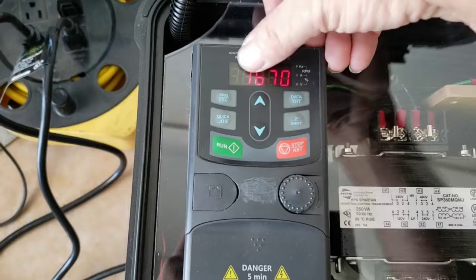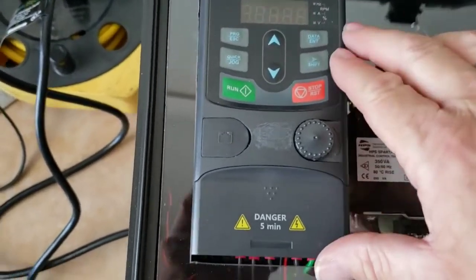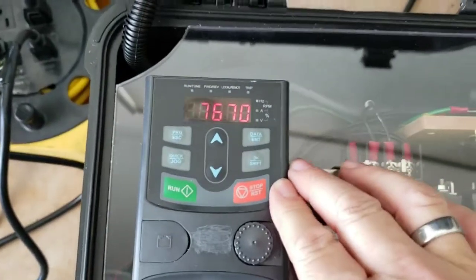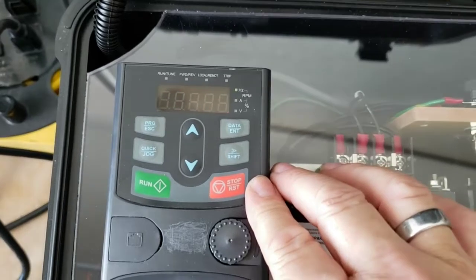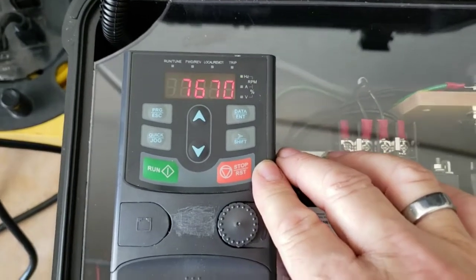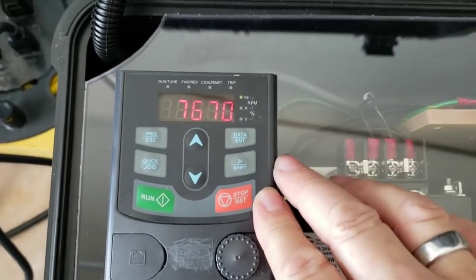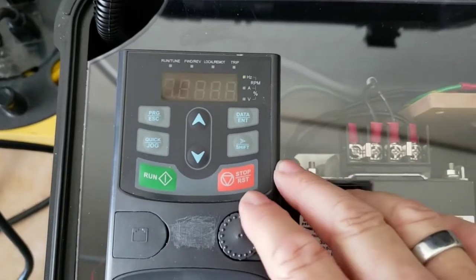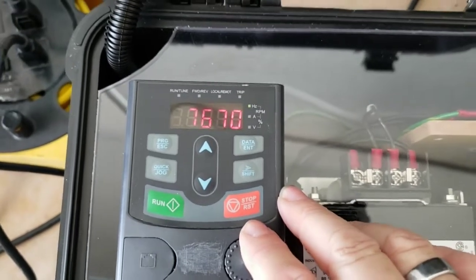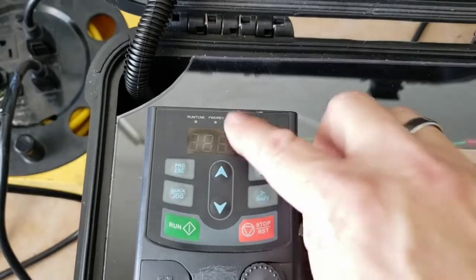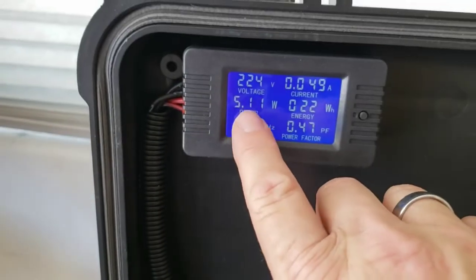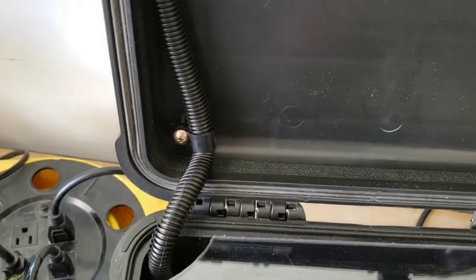Personally, I like the frequency one is the most relevant, because that one makes it really easy to tell if the unit is tuned properly for a given cell. So if you get a bad cell, that number doesn't work properly. It goes out of range. And of course, you're also looking at the wattage. So between the frequency on this screen and then the wattage on this screen, those are the two relevant values that you generally watch when you're trying to check for a bad cell.